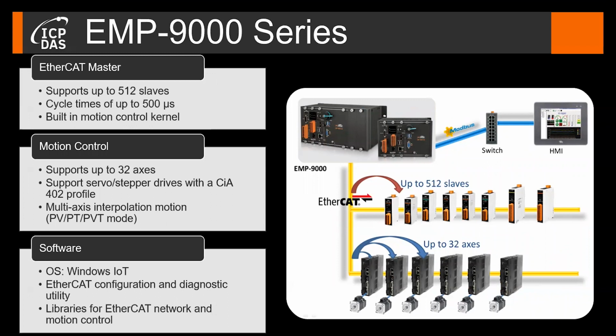Our EMP9000 series is ICP DAS's EtherCAT-based programmable automation controller with main focus on motion control applications. The device comes with a pre-installed Windows IoT operating system. The built-in motion engine, together with the EtherCAT master, runs on a dedicated processor in a real-time environment to achieve time-deterministic control of the EtherCAT application. The multi-axis motion control kernel controls up to 32 axes. The stepper and servo drives, which meet the CiA profile specification, are automatically detected by the motion engine and can be put into operation without tedious configuration. Motion commands for single-axis and multi-axis synchronous coordinated movements like linear, circular and helical interpolation are all part of the library.